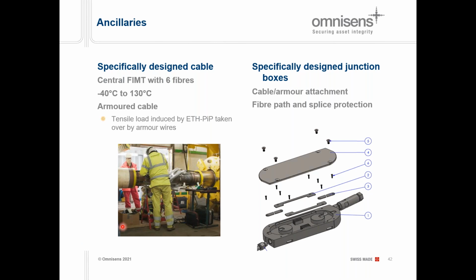So the cable itself is a central fiber in metal tube featuring 6 fibers, qualified for -40 to about 130 degrees C, and it has armor wires around there which are there to take over the load on the cable during the spooling, transportation, and the installation. There is also a dedicated junction box that goes in between the two pipes. That's what the colleague was doing, with a mechanism to lock the cable, and then the position in the center where we can handle the splice and the splice protection.